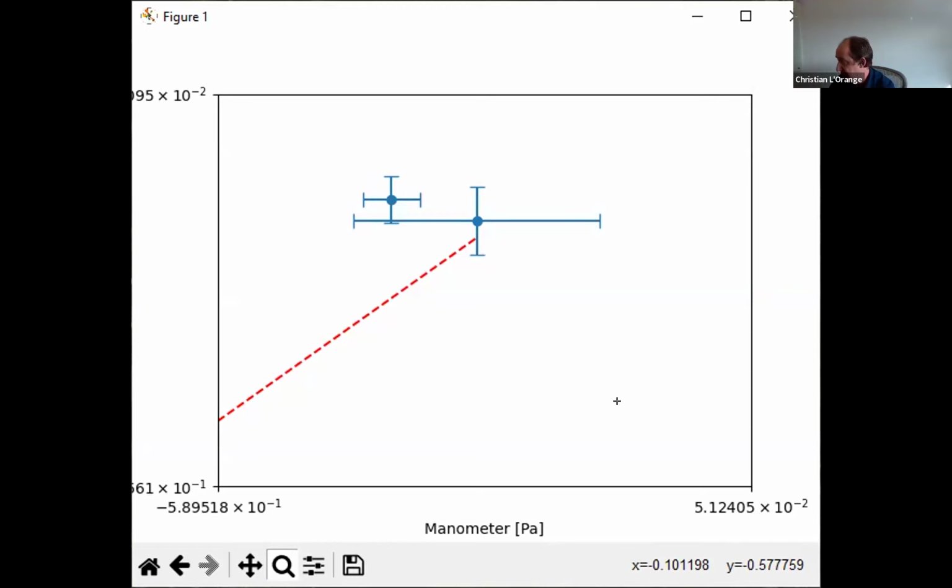I'm just going to have Carson change it from 1 second logging to whatever you guys are using as your logging interval. Is it 5 seconds, John? For the manometer itself, it's 5. Yeah, let's just do 5. We often average it beyond that, but you can't unaverage things. Okay, I'll have it keep polling at 1 second and we'll average to 5, just so we're on the same time step as you guys.